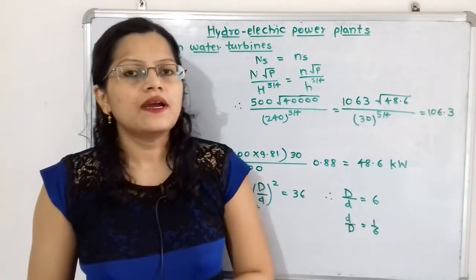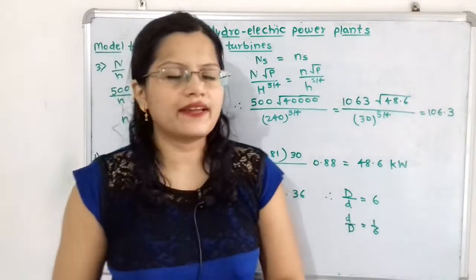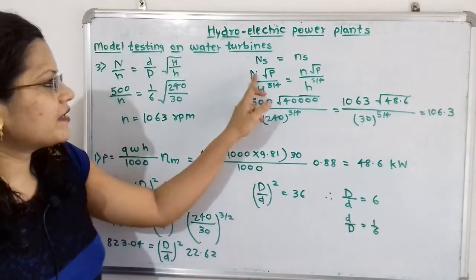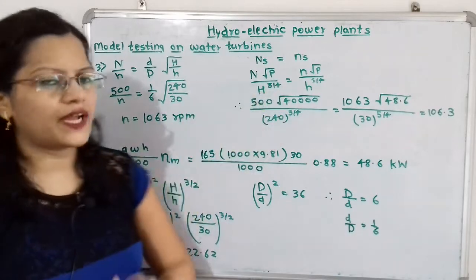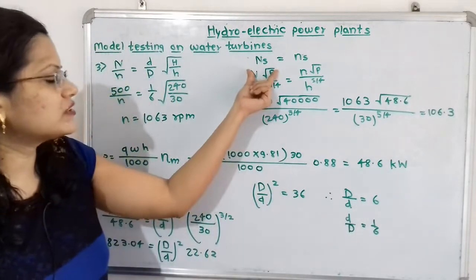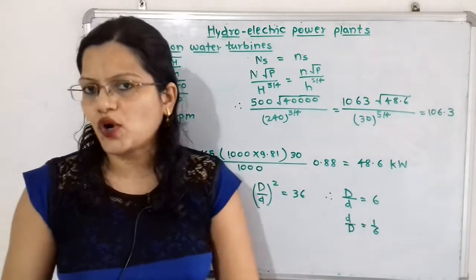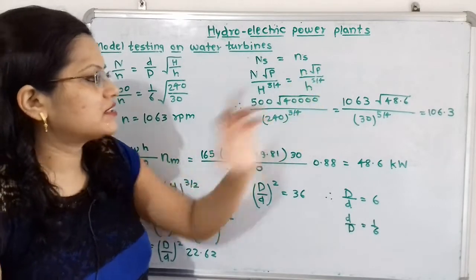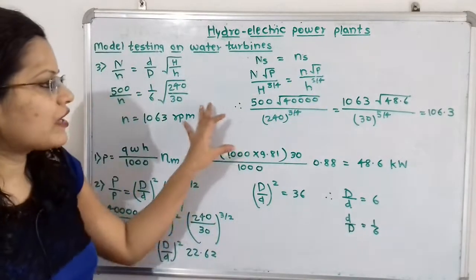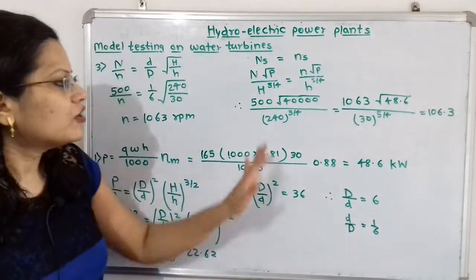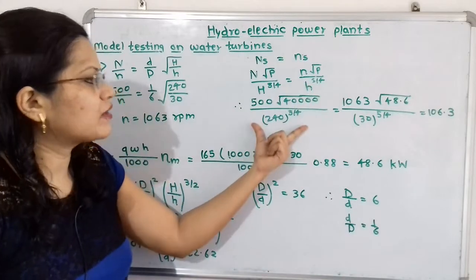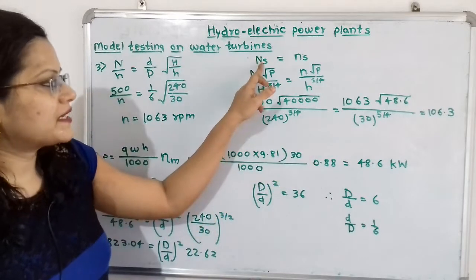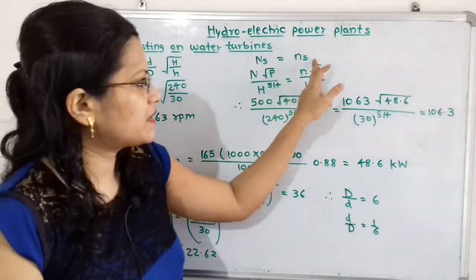The specific speed of the model and prototype should be the same, so capital Ns equals small ns. The formula is N times the square root of P, divided by H raised to 5/4. Using capital letters for the prototype and small letters for the model, all values are now known. When we calculate, the specific speed of the prototype equals the specific speed of the model, and both equal 106.3, which confirms our results.